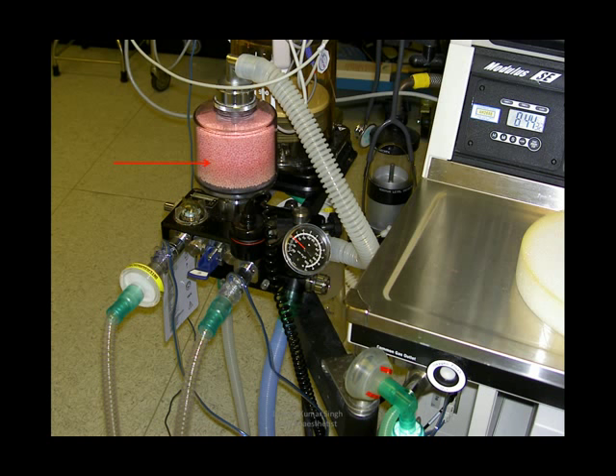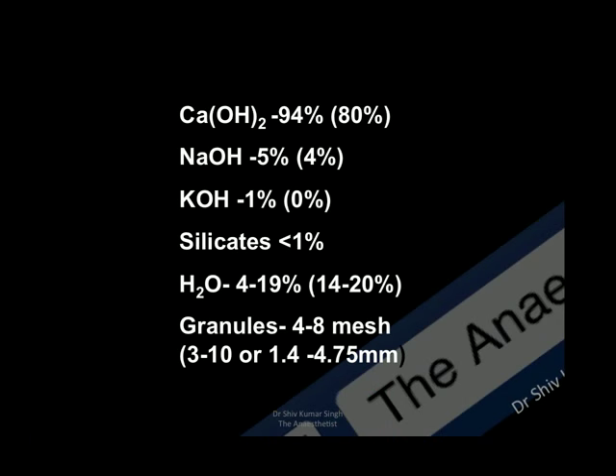The most important component of a circle system is the soda lime. The soda lime consists of calcium hydroxide, sodium hydroxide, and potassium hydroxide — which is not used in new soda limes because it is very caustic. Silicates were used in the older soda lime but not in the new ones. It obviously has water, the content of which can vary from 14 to 20 percent. The granule size is around 4-8 mesh size.